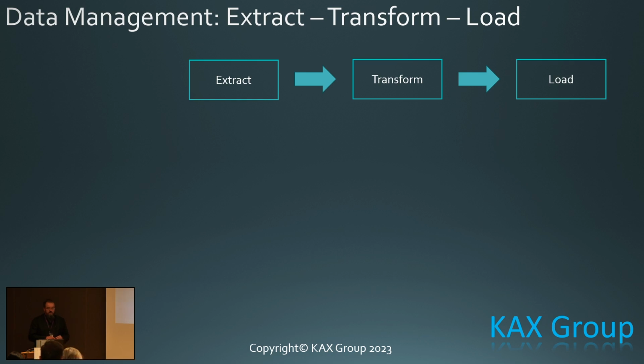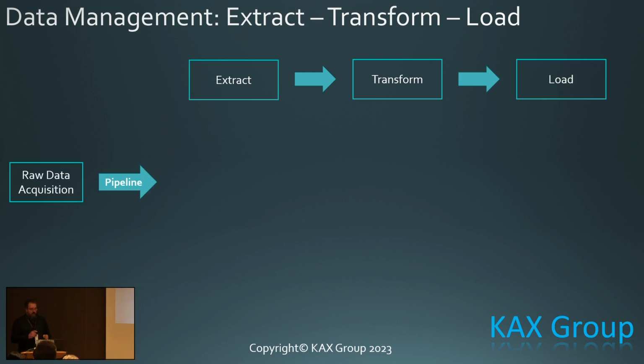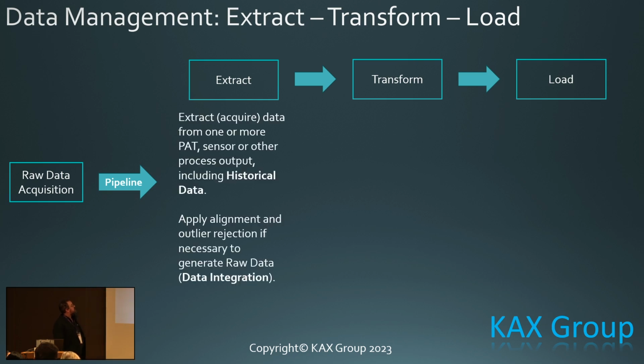So this brings me to the data management extract, transform, load principle. If you acquire raw data from an instrument, you bring it down the pipeline, coming from the instrument into the data modeling or deployment system. We extract or acquire data from one or more PAT sensors or other processes, including historical data. We apply alignment and outlier rejection if necessary, and we can generate a single spectrum or an array of data, which may be a composite of two spectra, if you've got a Raman, mid-infrared, and say other sensors working in place. That's your raw data, a snapshot in a single format, which is uneditable, and has a timestamp and records all the metadata associated with collecting that data.